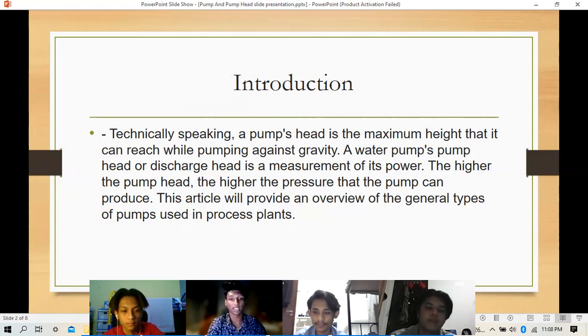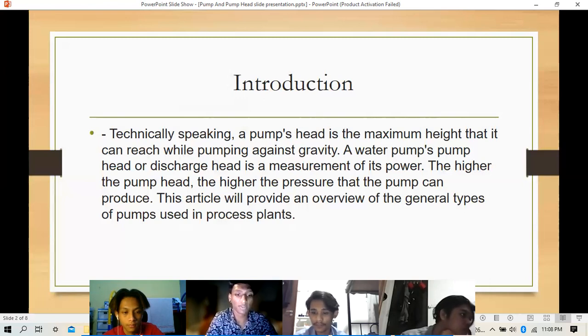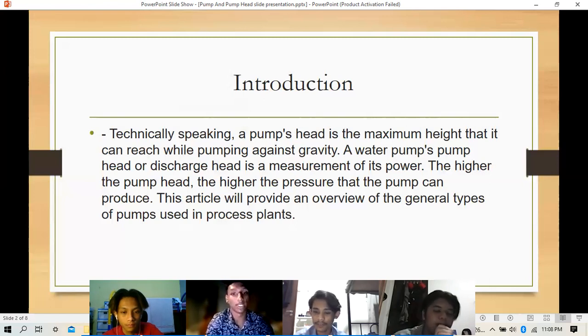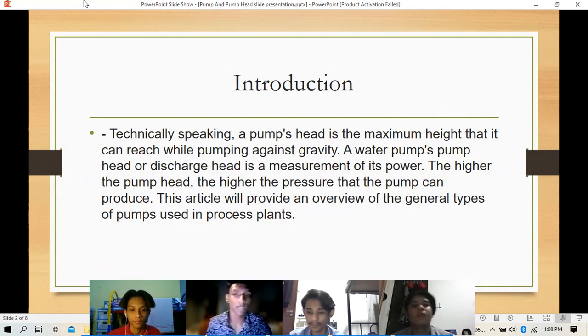The total head is calculated by subtracting the head in the vertical discharge pipe from the level of water in the tank. When the amount of water in the discharge tank rises, so does the head in the discharge pipe. Because the water level in the tank is lower, the head is reduced. Manufacturers cannot provide an accurate level of the head since they do not know how much water will be in the tank. No matter how much air is in the tank, the total head will remain constant. However, the water level in the tank will affect the discharge pipe head. That's all from me. Thank you for listening to my presentation. And next will be Hafiz.